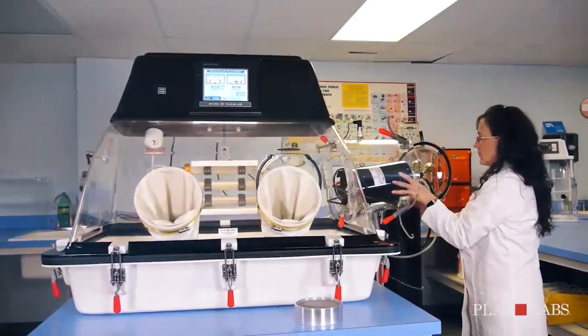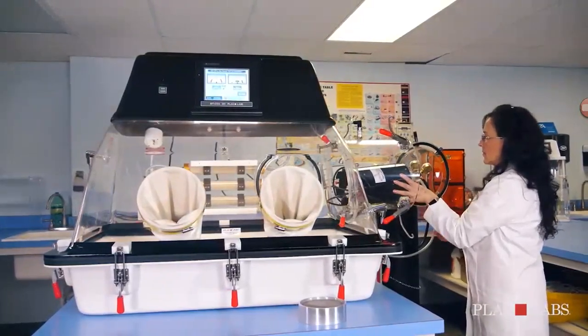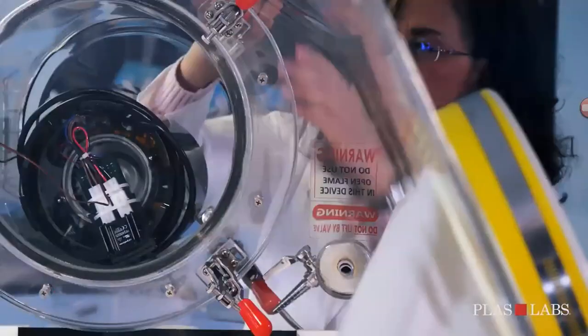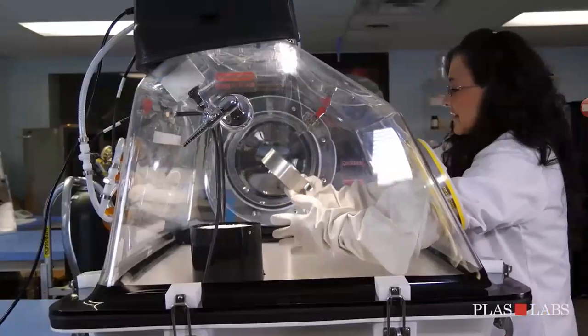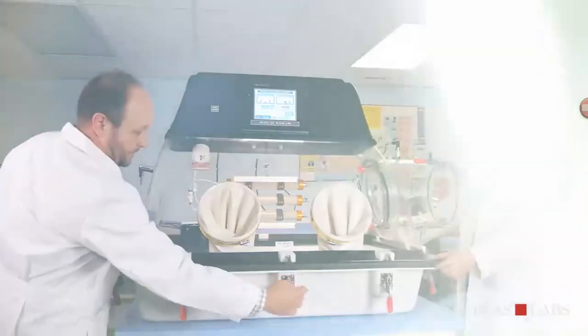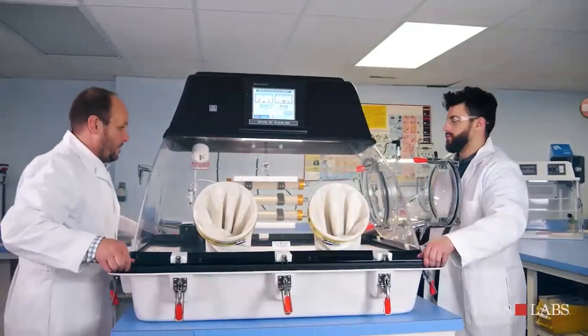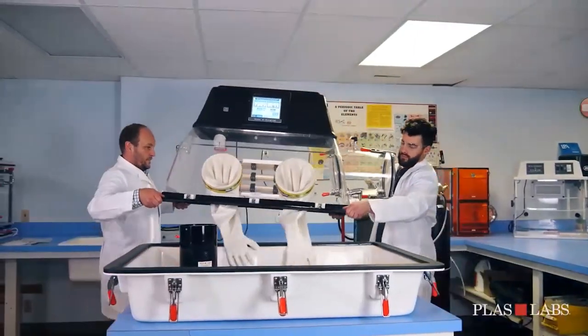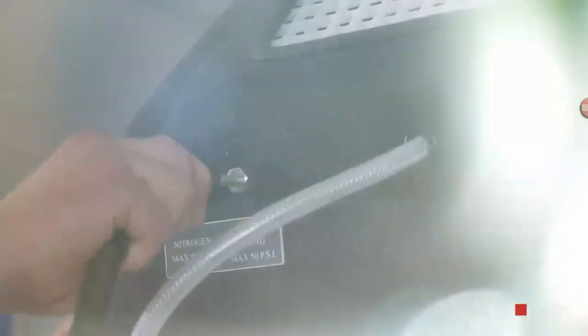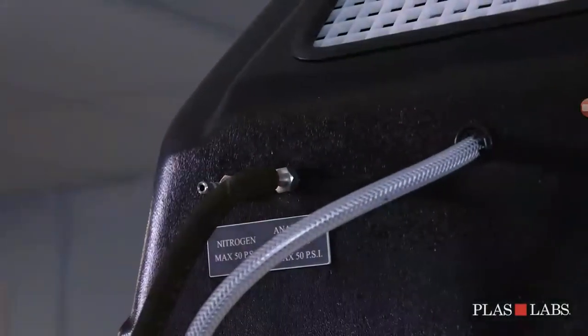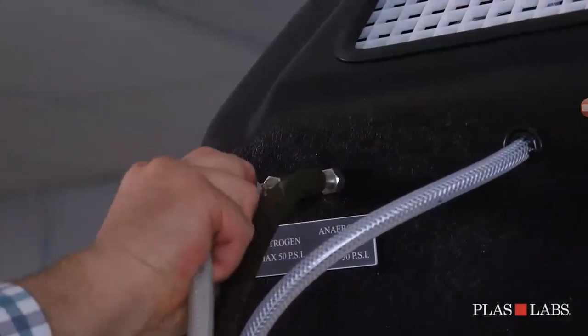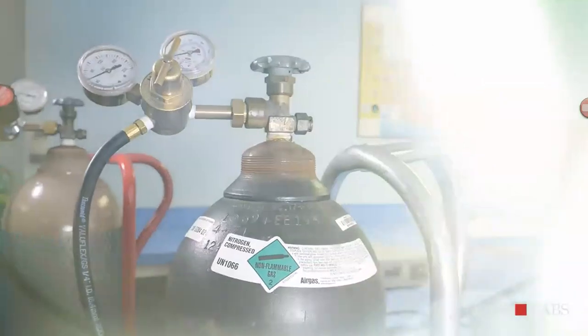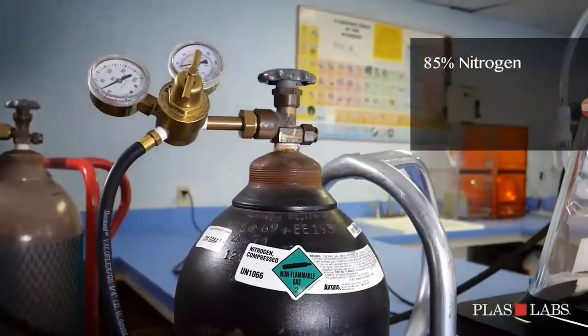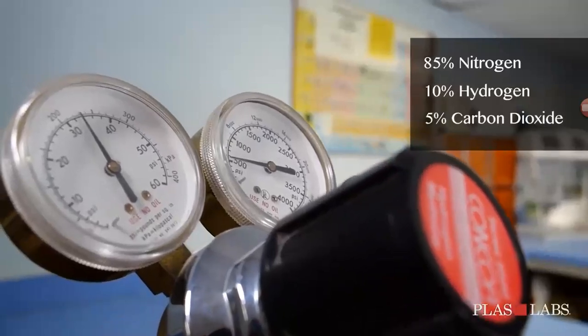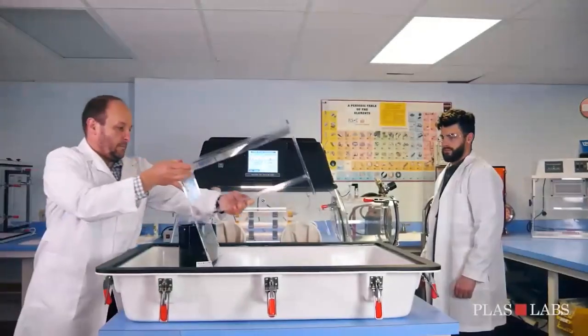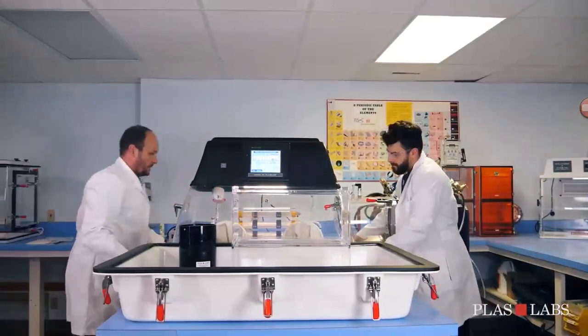To begin, place the programmable catalyst heater unit and palladium canister inside the glove box. Do not turn the catalyst heater on. Place the palladium canister next to the heater. For larger equipment, such as balances, shelving units, shakers, or stirrers, you may remove the clear acrylic top from the one-piece bottom. Using a quarter-inch hose, connect the nitrogen gas and the anaerobic gas mixture to the valves located on the back shroud. The anaerobic gas mixture consists of 85% nitrogen, 10% hydrogen, and 5% carbon dioxide. Once your desired equipment is inside the glove box and the gas is connected, you are ready to begin purging your glove box.